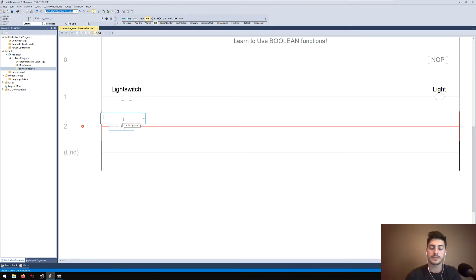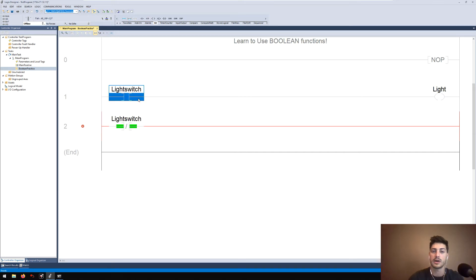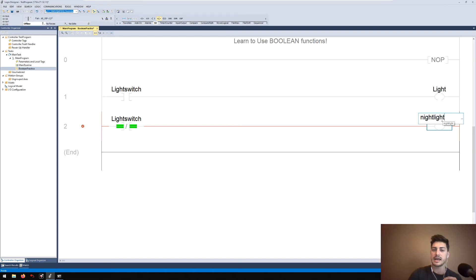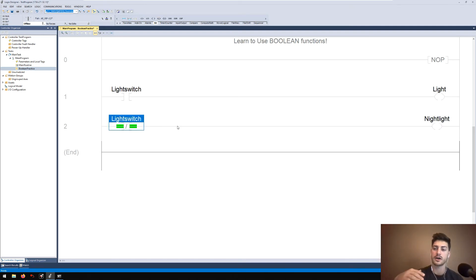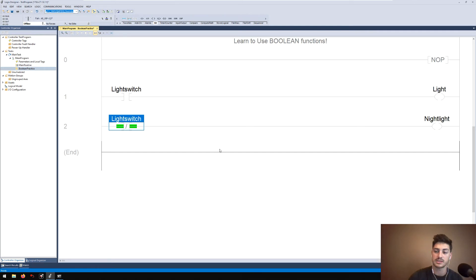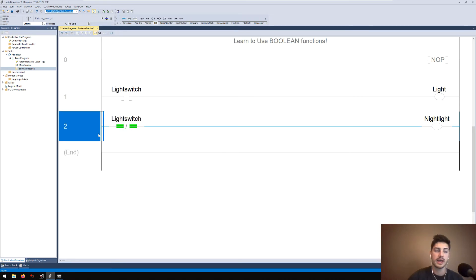Let's add another rung using an XIO to demonstrate what happens when the light switch is off. You don't need one of each — a single rung is perfectly valid — but let's say when the light switch is off, we energize a night light. So we're saying: if the light switch is off, the night light is on; if the light switch is on, the overhead light is on. With just these two rungs, the opposite state is automatically off, because an OTE is only active while the conditions on that rung are true.